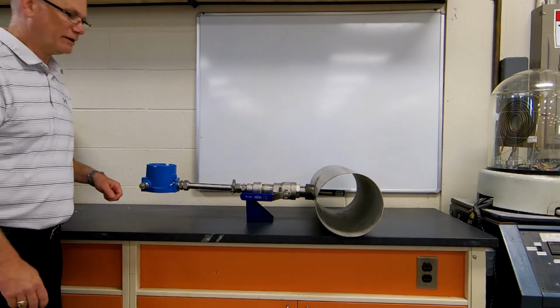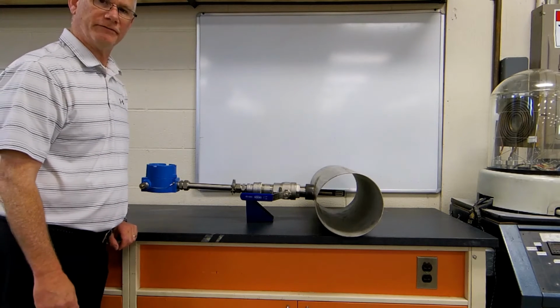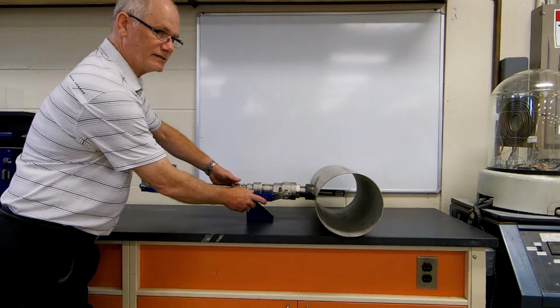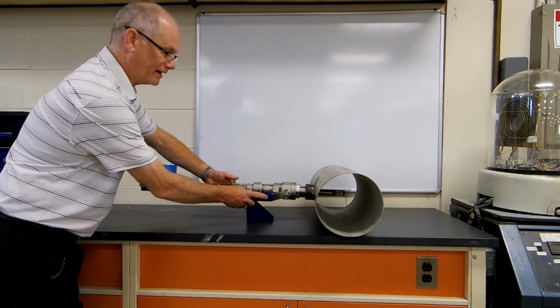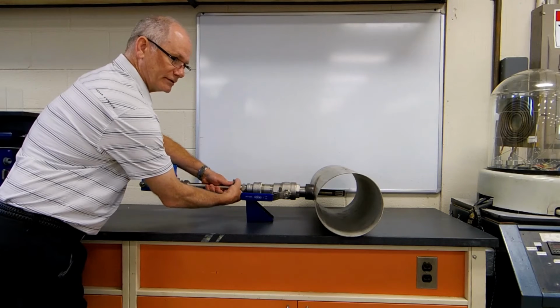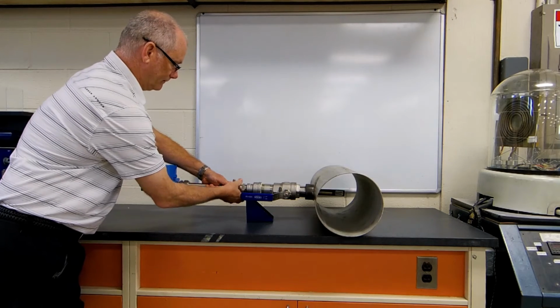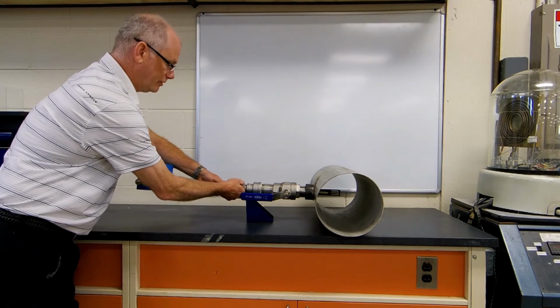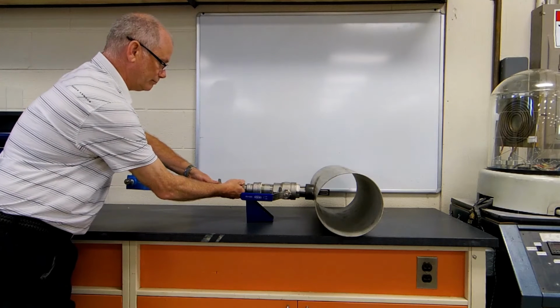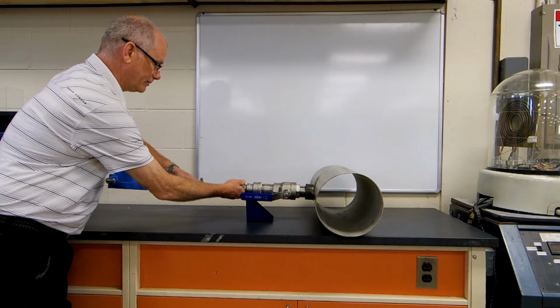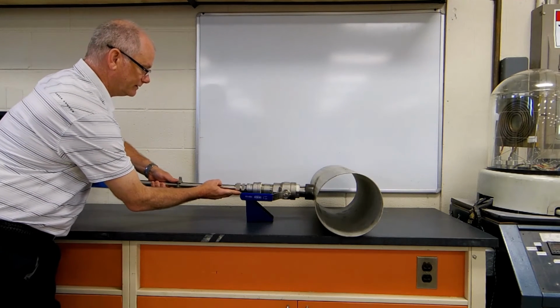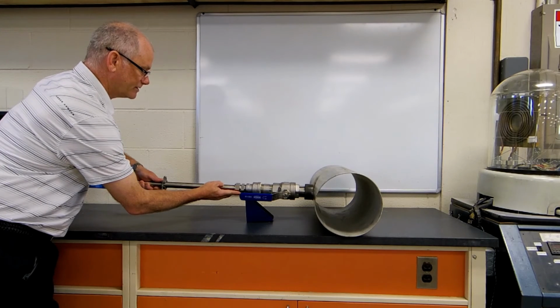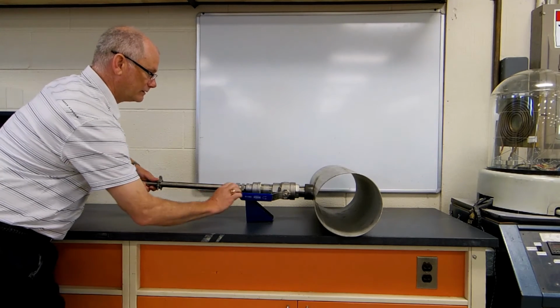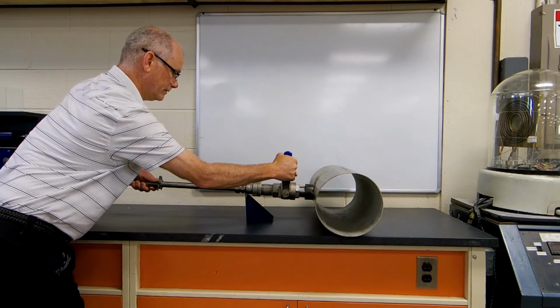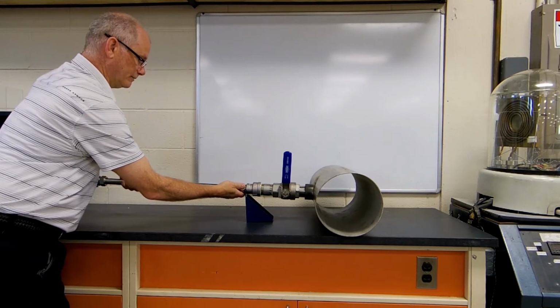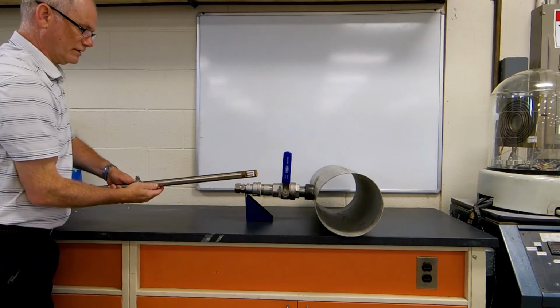The RheoVac probe can be removed from the vent line while under vacuum by utilizing the extraction mark on the probe shaft. First, loosen the compression fitting and firmly pull the probe out of the vacuum line until the extraction line is visible. Close the ball valve assembly and remove the probe the rest of the way from the vent line.